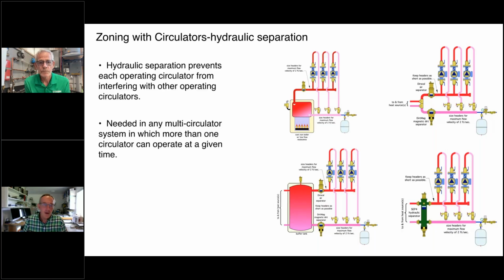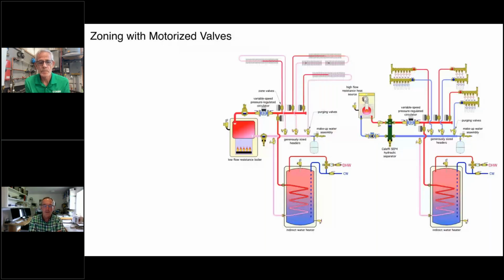Okay, so now we've talked about zoning with circulators. Let's switch over to motorized valves here. And these are basically the same 2 systems. All I've changed is the method of zone control. So we've got electric zone valves here. And in this case, I'm showing a variable speed pressure regulated circulator. We're going to talk about differential pressure control coming up here.